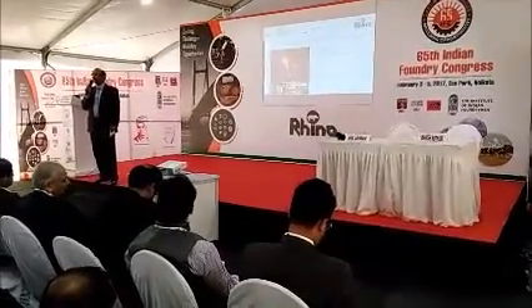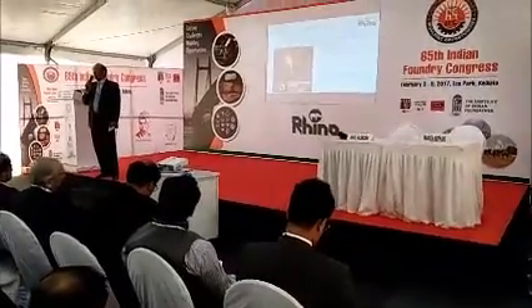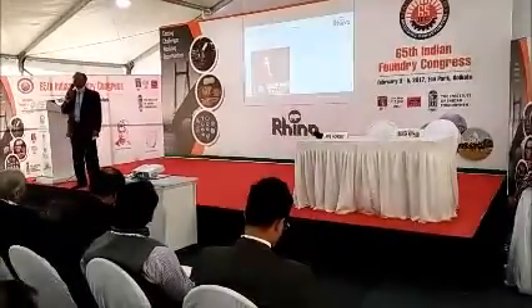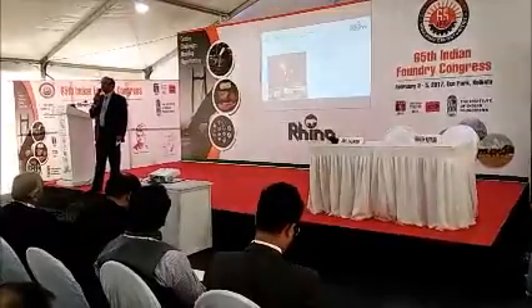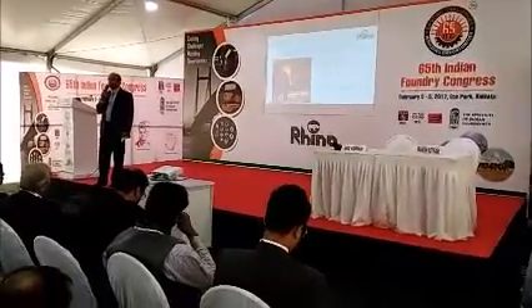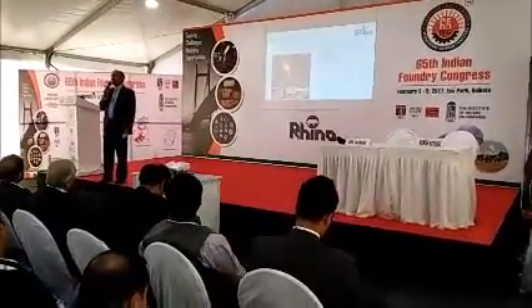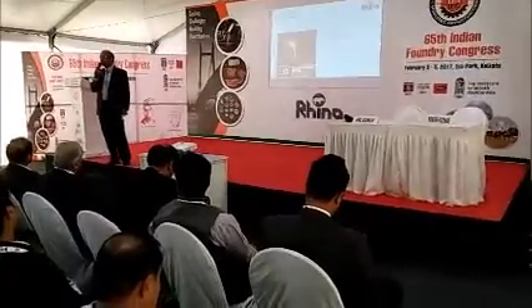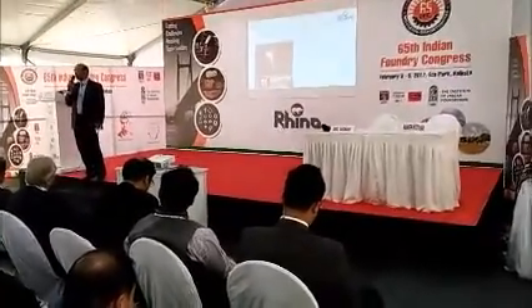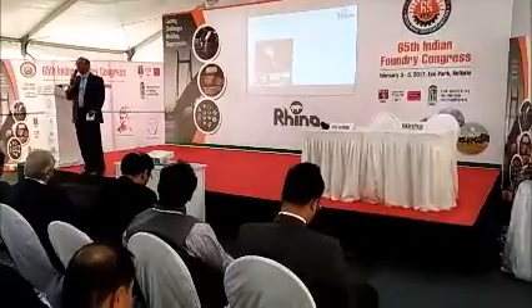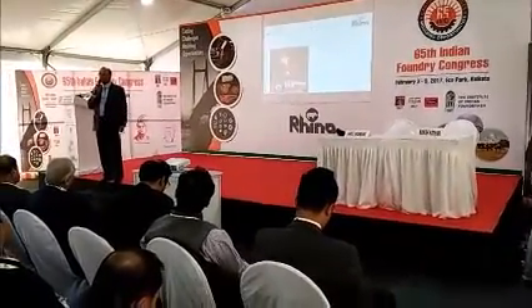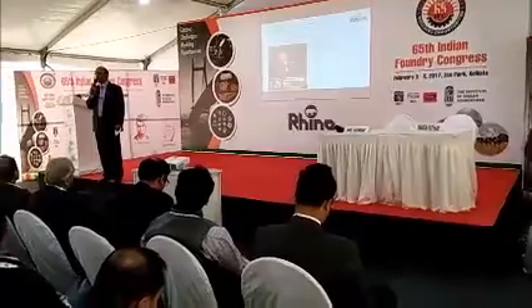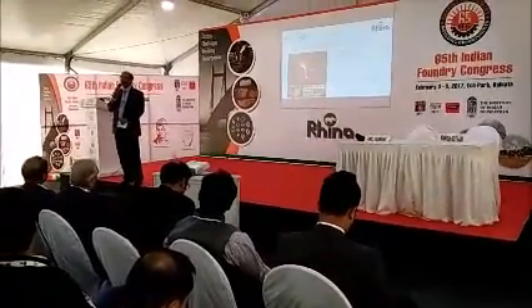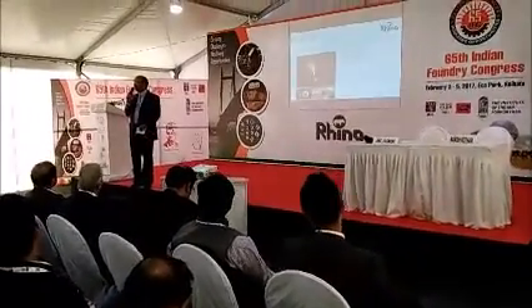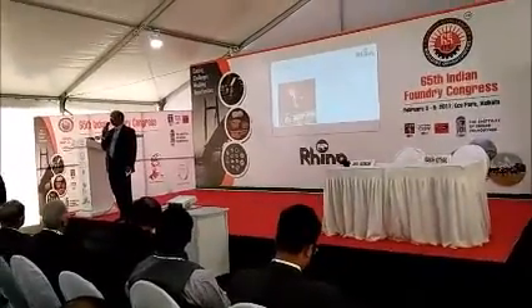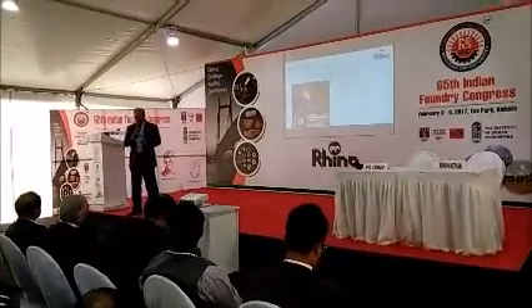So all data is to be collected correctly, and many of the people have installed energy meters at different places, but energy readings are taken manually. In 24 hours, suppose you have 10 energy meters at 10 locations, people keep on moving at different places, and instead of 8 o'clock, the energy meter reading is taken at 8:20 or 8:30, so you don't get correct data of 24 hours, but you calculate that data on your 24 hours production. So there is always error in getting the data and analyzing it correctly.